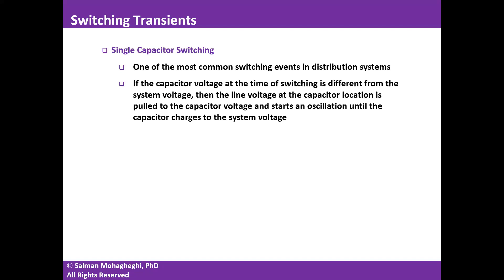We're going to start the discussion by looking at the most common switching event in distribution systems — switching on a single capacitor bank. Let's consider a scenario in which I have a voltage source representing my power system connected to a particular capacitor bank. This is L_S, which is my source inductance, and this is my capacitor.